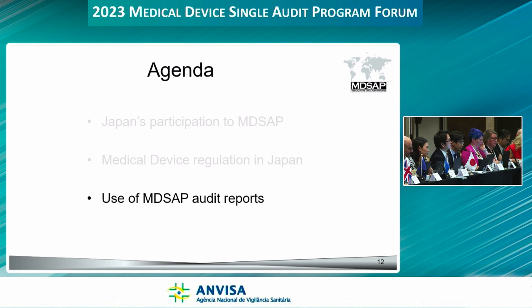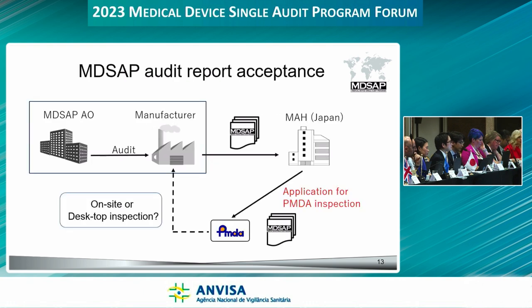Finally, I will show how the MDSAP audit report is used in Japan. This is an example of a manufacturer that has obtained a certificate and MDSAP audit report. The marketing authorization holder, who is the applicant for the QMS inspection of the product manufactured by the manufacturer, obtains the MDSAP audit report from the manufacturer and submits it with the QMS inspection application. PMDA reviews the application and the MDSAP audit report and determines how they conduct inspections, as I mentioned earlier.